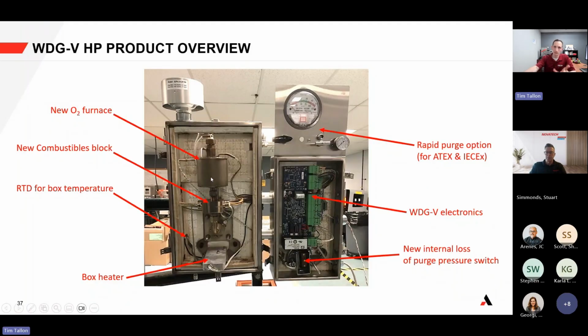That furnace is similar to that of the WG5—smaller cells, tighter, making a much more precise measurement and monitoring. So: new furnace, new combustible block, better stability of the combustible measurement to maintain temperature. As you maintain temperature on the combustible block, you also maintain accuracy—so stronger accuracy on the combustible block.